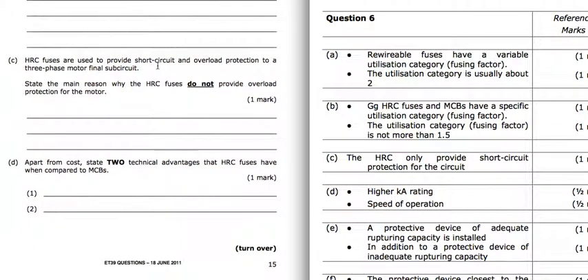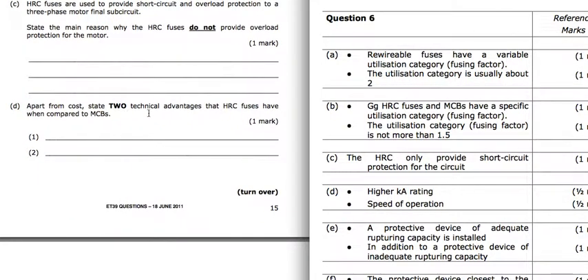HRC fuses are used to provide short circuit and overload protection to three-phase motors. State the main reason why the HRC fuse does not provide overload protection. The HRC fuse is there really for short circuit protection. So it's able to break a very high current, and that's what it's there for, to provide short circuit protection. Apart from cost, state 2 technical advantages that HRC fuses have compared to MCBs. So one of those is that higher kiloamp rating, that higher short circuit protection, and it's also faster acting, so the speed of operation.